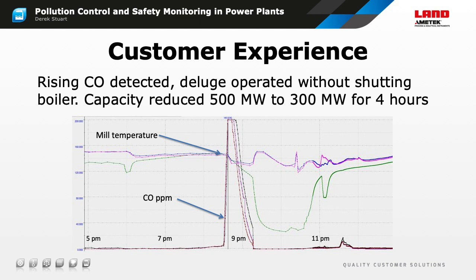The mill came back into service just before 11 pm, and you can see a small spike in CO as the fuel was introduced to the mill. In conclusion, they had a potential fire or explosion which was avoided, and the only consequence was to reduce output for 4 hours.